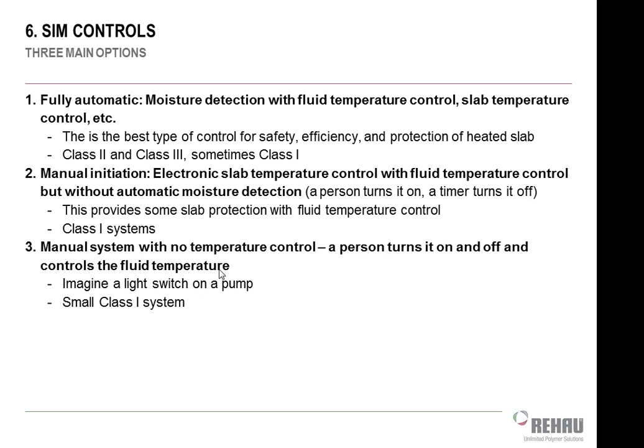The problems with that are if you're not there to turn it on, obviously it's not going to do anything. And once you accumulate 6-7 inches of snow, turning it on is not going to help you much because it's going to melt the snow on the bottom, and then the cold snow on top is going to re-ice that continuously. So a manual system is generally frowned upon, and we don't install those systems out of our office.